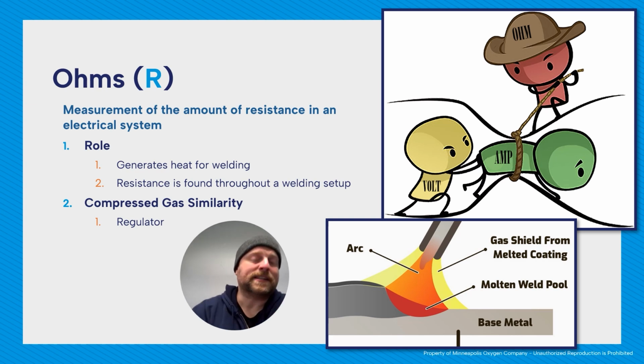This is really important when doing code welding and qualifying procedures, because you have to actually test what the power is coming out at the arc. The machine might say 120 amps, but because of connections, frayed wires, whatever it is, maybe you're only getting 100 at the end of your electrode holder. That's why you would check that out.